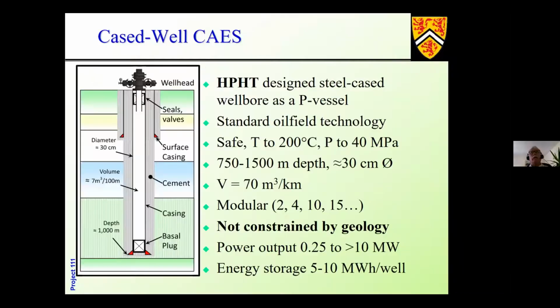Another way of storing compressed air is using a cased wellbore. The nice thing about a cased wellbore in the subsurface is that when we put in a 30 or 38 centimeter diameter wellbore in a drilled well in granite, shale, limestone, or sandstone, this is independent of the geology. We can cement that steel cased well in place, and the surrounding earth provides the confinement. So now we can use that wellbore to store gas up to maybe 40 or 50 megapascals, depending on the design, and up to 200 degrees Celsius. The well can be 500 meters deep, 1,500 meters deep; deeper is unlikely.